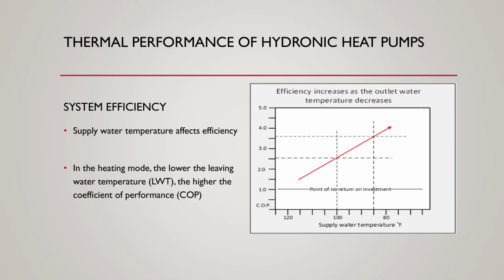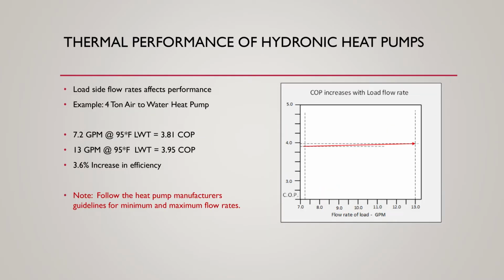So if you guys aren't familiar with a concept called outdoor reset, it's a huge benefit with hydronic heat pumps. As it gets milder out, we can heat with lower and lower temperatures, and that's got a doubling effect because not only is the heat pump working more efficiently because it's warmer out, it can operate more efficiently at those lower temperatures we can still heat with. And then flow rate also affects efficiency. Not by as much, but it's still important. The big thing with flow rate is if you don't have enough, you're going to start damaging your heat pump: overpressurize the refrigeration circuit, or low suction pressure when you're cooling.